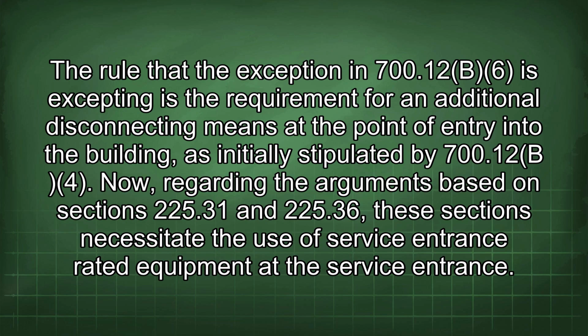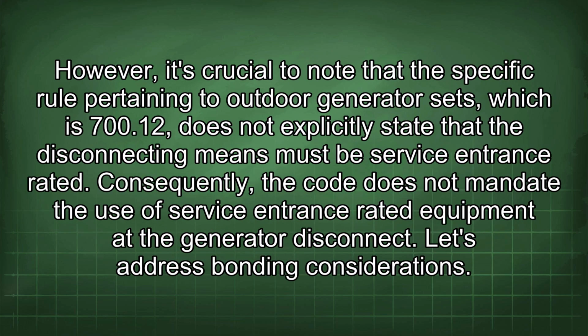The rule that the exception in 700.12(B)(6) is excepting is the requirement for an additional disconnecting means at the point of entry into the building, as initially stipulated by 700.12(B)(4). Now, regarding the arguments based on sections 225.31 and 225.36, these sections necessitate the use of service entrance rated equipment at the service entrance. However, it's crucial to note that the specific rule pertaining to outdoor generator sets, which is 700.12, does not explicitly state that the disconnecting means must be service entrance rated.